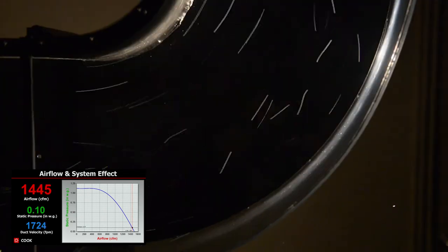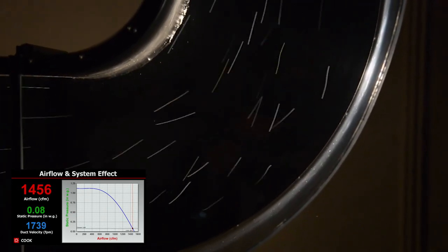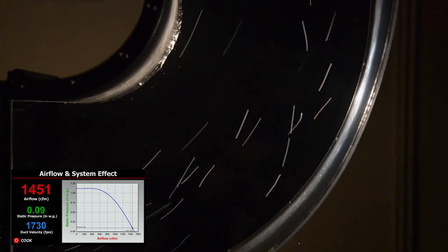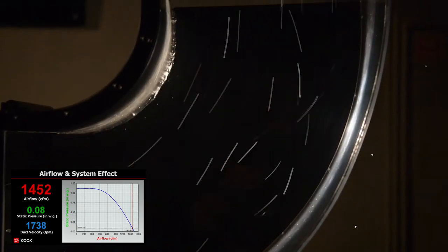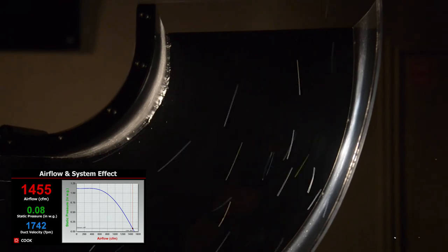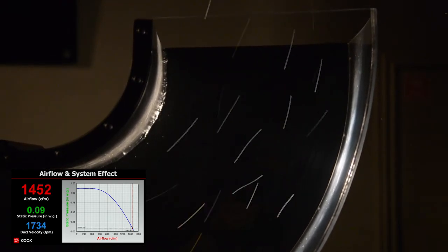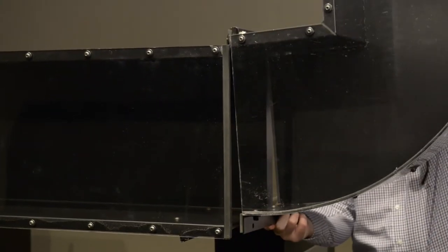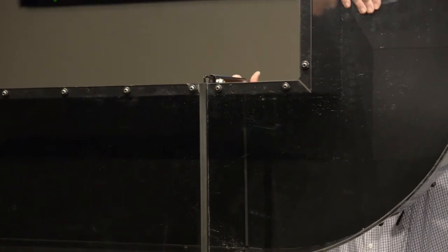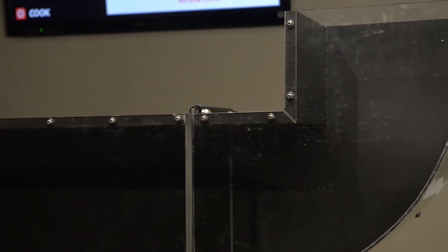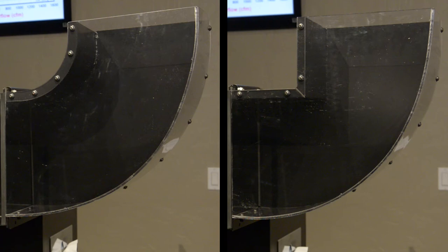Short radius elbows are compact, yet have minimal pressure loss. This elbow is also less costly than a square elbow with turning vanes. In this case, 22% less expensive. The third fitting is a short radius elbow with a square 90-degree throat. It takes up the same space as the short radius elbow, but is cheaper to make.